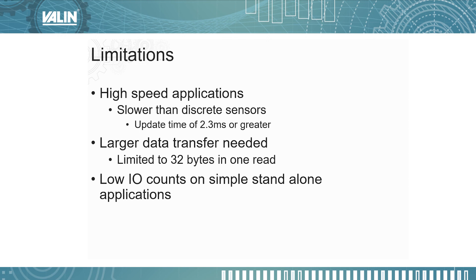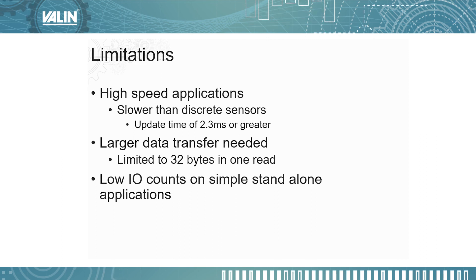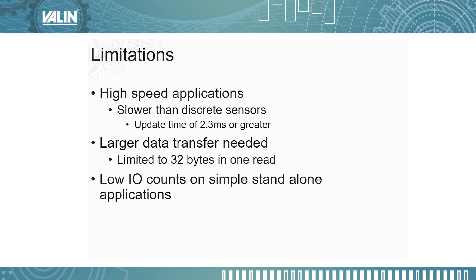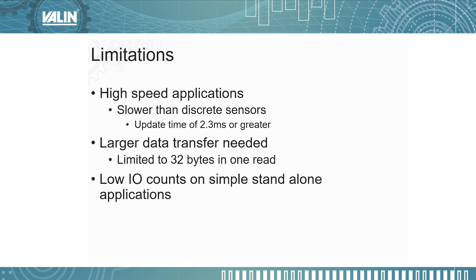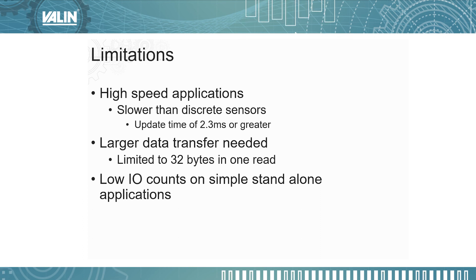What are the limitations of IO-Link? For high-speed applications, most discrete IO-Link sensors have an update time of 2.3 milliseconds or greater, so if you can't live with that update time, you'll need to go with a standard IO device. If you have a large amount of data that needs to be transferred from the device to the controller, IO-Link is a poor option because it's limited to 32 bytes. And for smaller machines with low IO counts on a simple standalone PLC, like a brick PLC, IO-Link is probably not a great option either. That's it — I know that was quick, but we're just hitting the highlights. Please look for subsequent videos showing how to use IO-Link devices with Omron N-Series PLCs and their IO-Link masters.